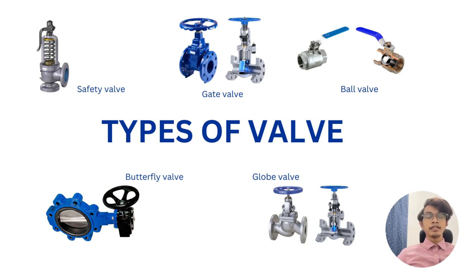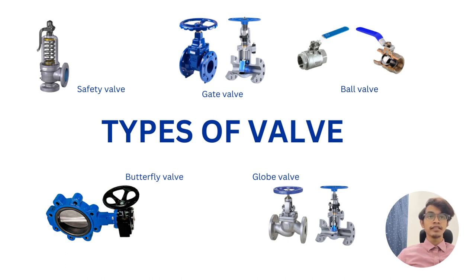The second is the gate valve. As the name suggests, the gate valve consists of a gate that can be raised or lowered into a passageway. The gate is at a right angle to flow and moves up and down in slots that keep it vertical. When entirely closed, it is usually a wedge shape and tightened against the sides of the slot so that substance cannot pass through. If a gate valve is left in an intermediate or partially open state, the bottom of the wedge and the seat will erode quickly. Therefore, the valve should always be wide open or totally closed.